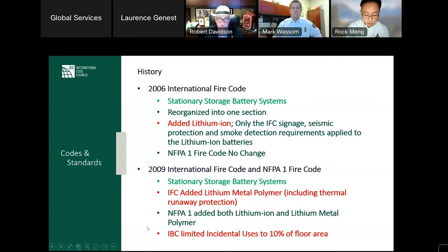2009, the fire code, both NFPA 1 and the 2009 code had changes. Still stationary storage battery systems. We added lithium metal polymer as a new technology, including thermal runaway protection. NFPA 1 added both lithium-ion and lithium metal polymer.